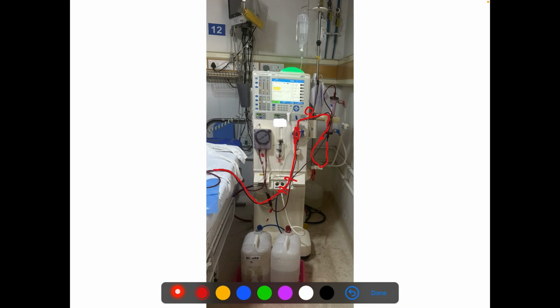So I will show again where the alarm will be shown. Okay, so these are the circuit of the blood. The blood part, and then there is another circuit which is the dialysate circuit. In the dialysate circuit, here we have a mixture of solution, here we have a bicarb, and this is your acid.